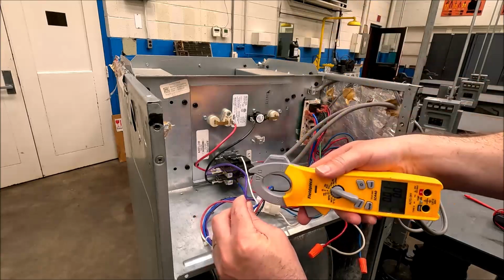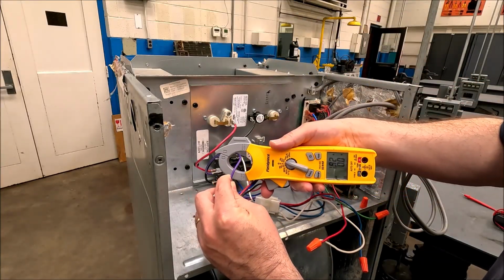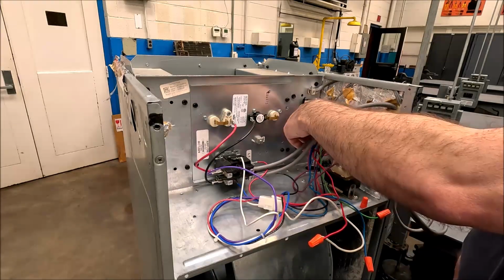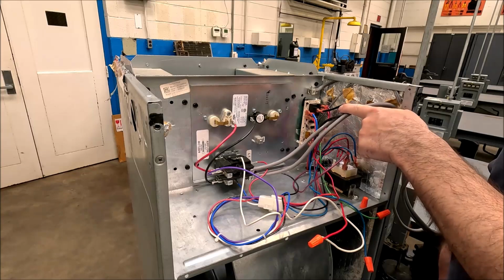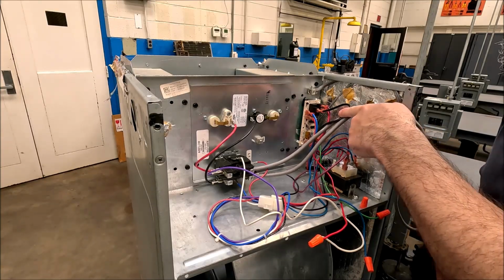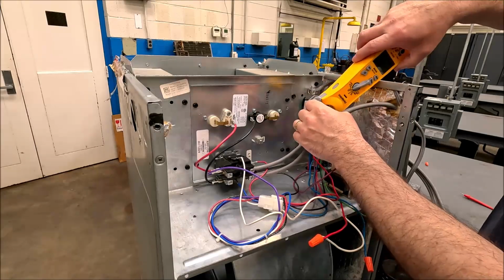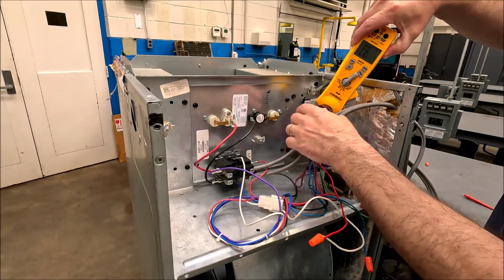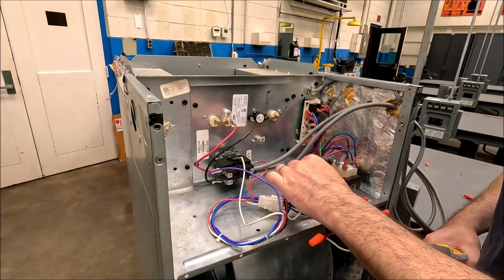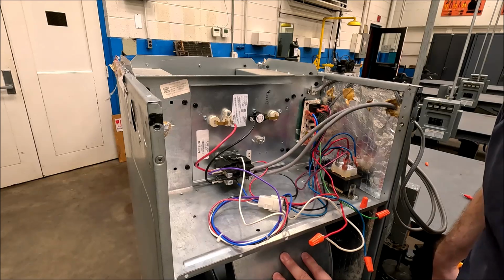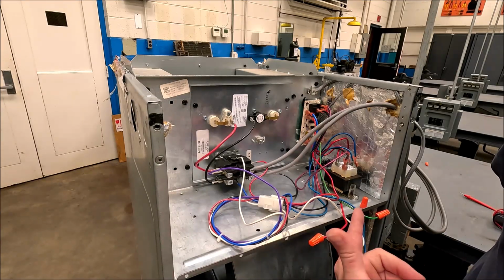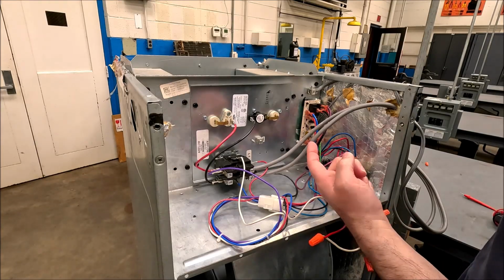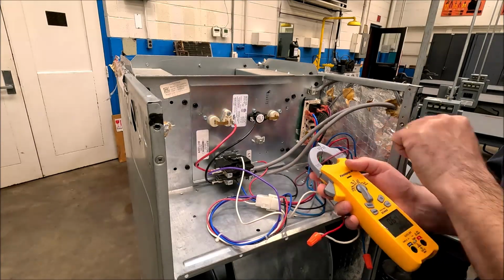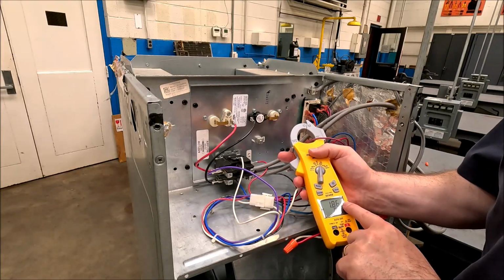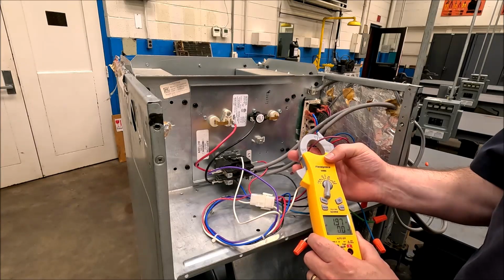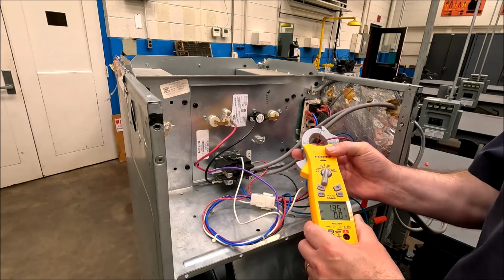first. So I know this purple wire is powering, so it's got 1.9, and if I come over here, I know that purple is going to my high speed, which is powering the motor, and it's going to be the same, 1.9. 1.97, yeah. But I do know that as it goes down to, because this is a 3-speed PSC motor, it does whatever it does on the run winding and the start winding, and then it comes back on this wire. It may not always be the same, but in our case it's 1.86, 1.98 if I hold it kind of centered. So it's almost verbatim the same.